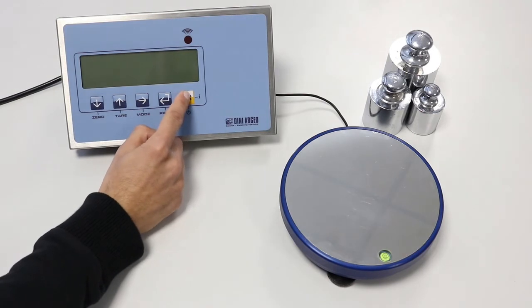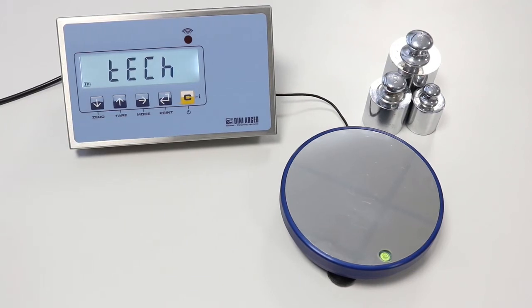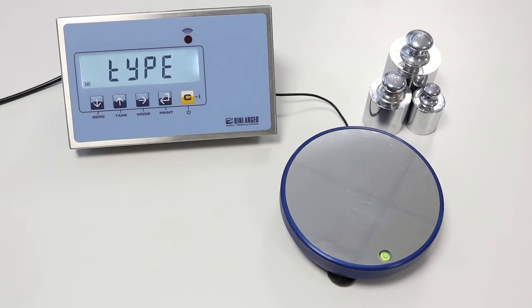Once turned on, this scale shows the technical message NO CAL, which means no calibration stored. To enter the programming menu, press the TARE key. Inside the menu, use the ZERO key and the TARE key to scroll up and down the parameters. Scroll down until SETUP and press PRINT.